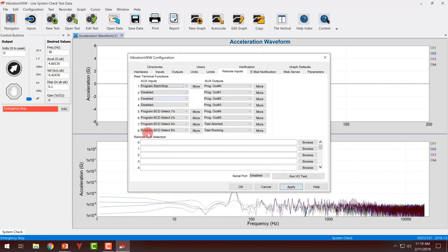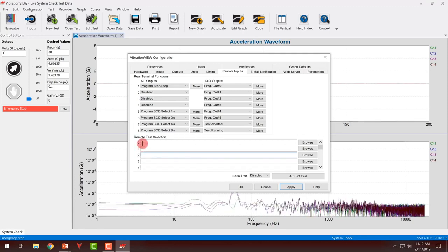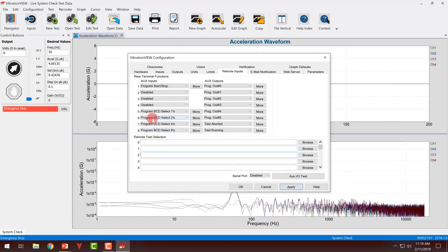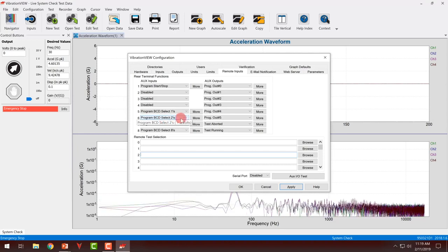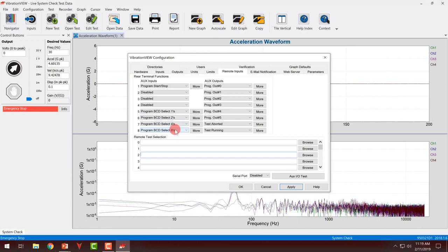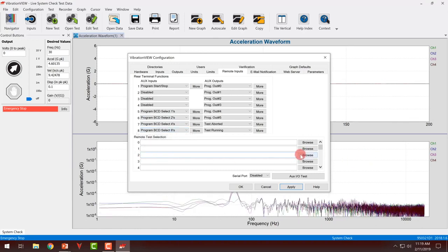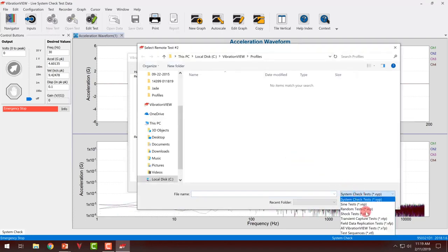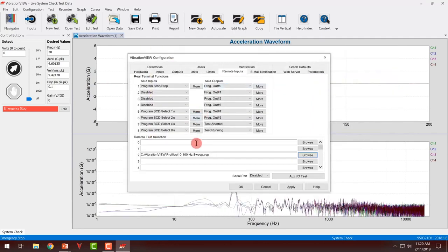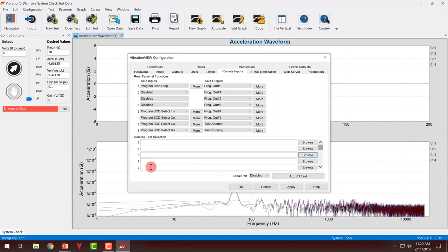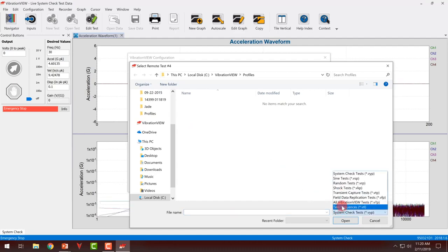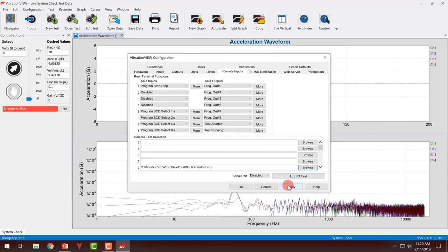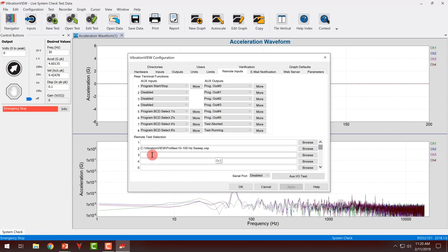Now I have to put some tests in my remote test selection window. Essentially, if I had a high input on channel six or auxiliary input six, which is my twos, so that would be a binary two if one, four, and eight were low, it would go to this location, whatever test I select, and start that test. If I hit browse, I can find a test profile. I just have a pretty simple sine sweep. I could also pick another one, let's just do seven. I can click apply. So I have a test on seven and a test on two.